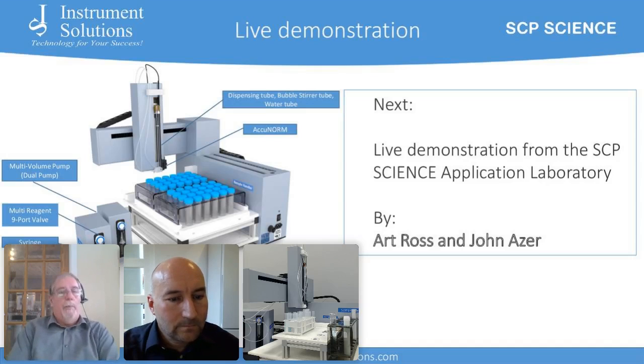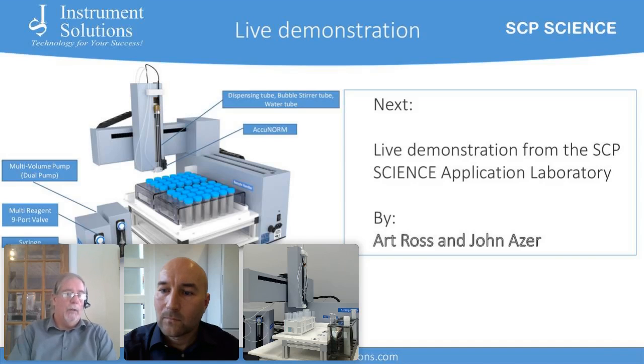So the pump has no metal parts that's producing the air. It's an onboard small pump, and if you're worried about using a pump and your lab air having contamination in it, you could connect it to an inert gas like argon or nitrogen. You need to provide about 5 bar, and the valve will use that gas as your bubble stirring media. Okay.